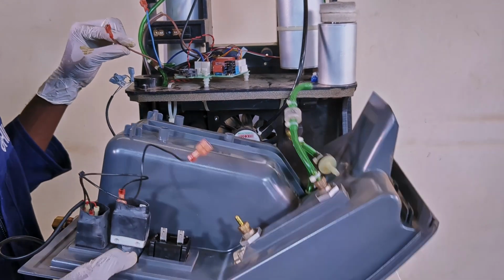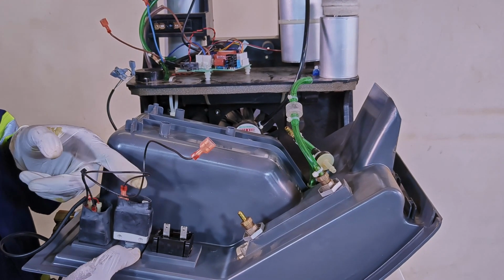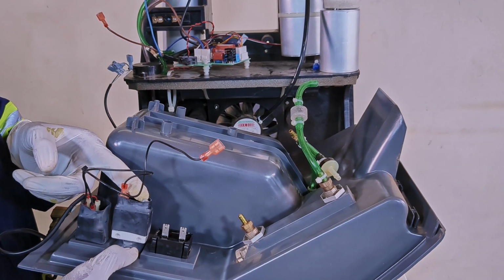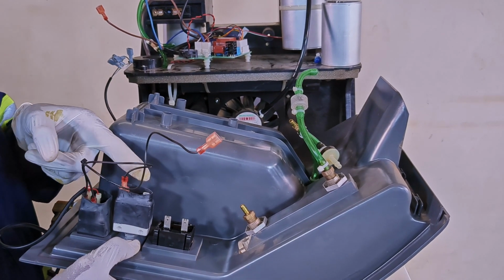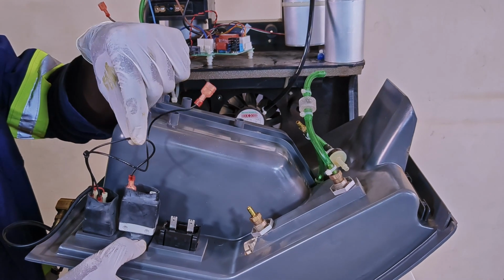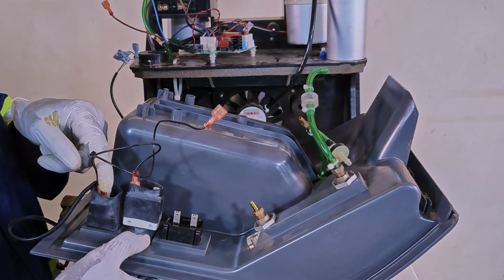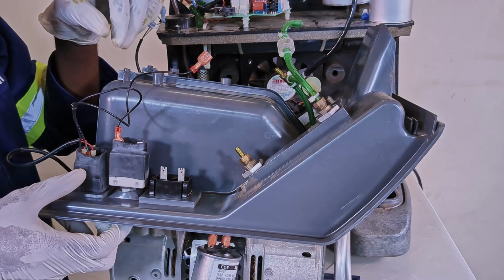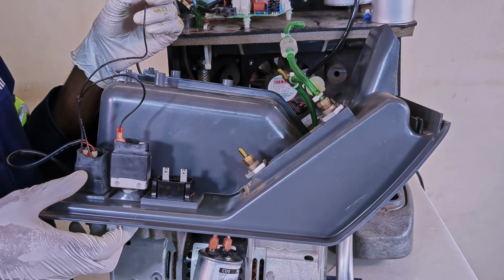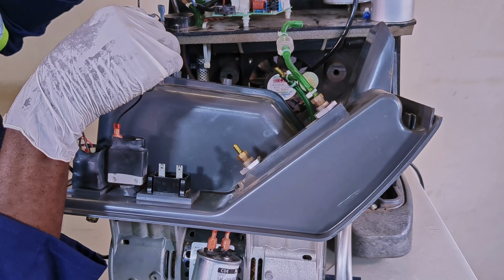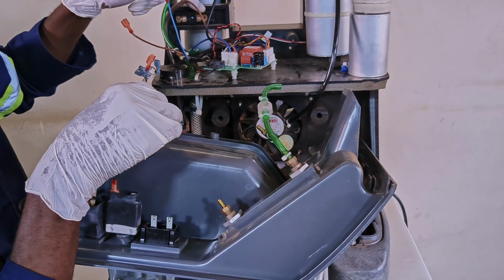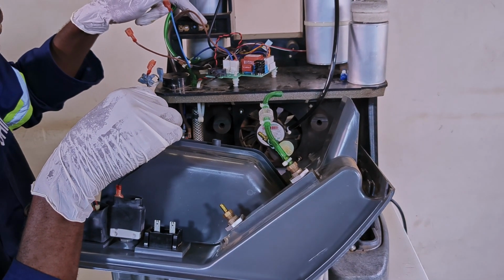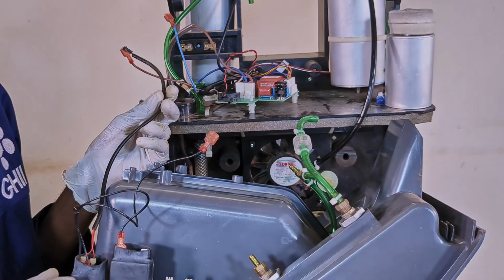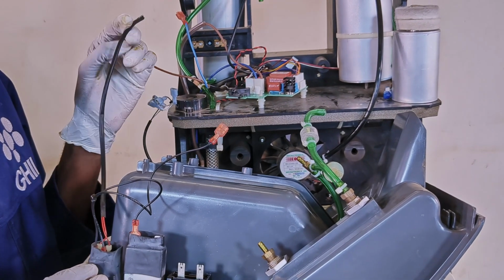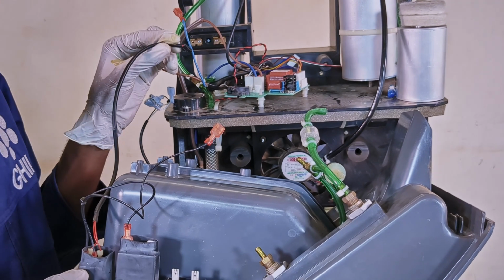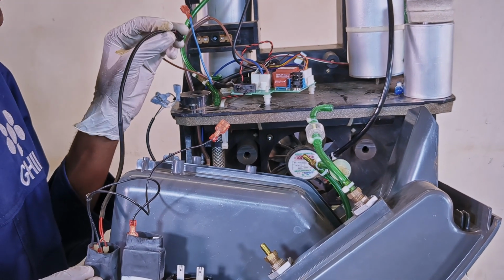This live cable is connected on the circuit breaker right here. From the circuit breaker, power is then tapped through this cable going to the power switch. And from the power switch, we have this cable here that is connected directly on the live connection part of the cable connector. This is used to distribute power to the other components. The power switch also has this plug cable. This cable is used to transfer DC output from the main control board to the switch.